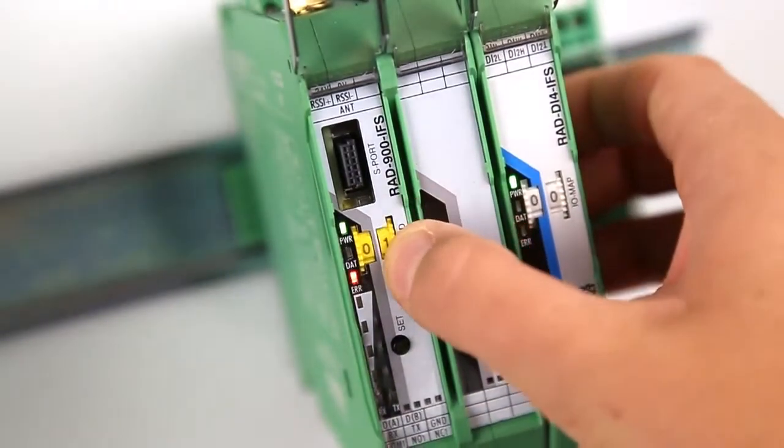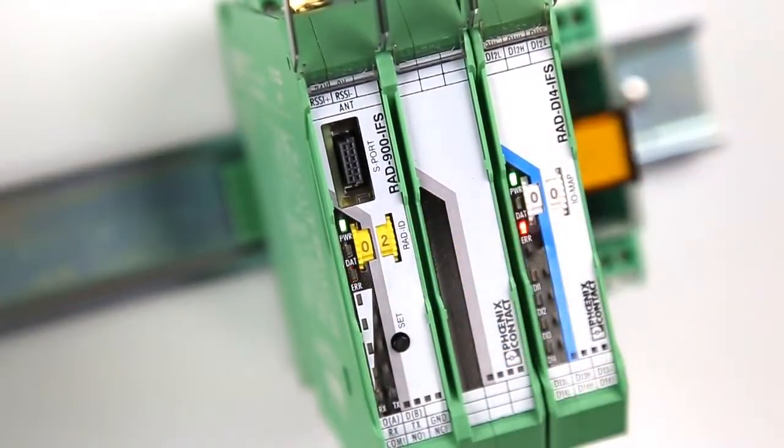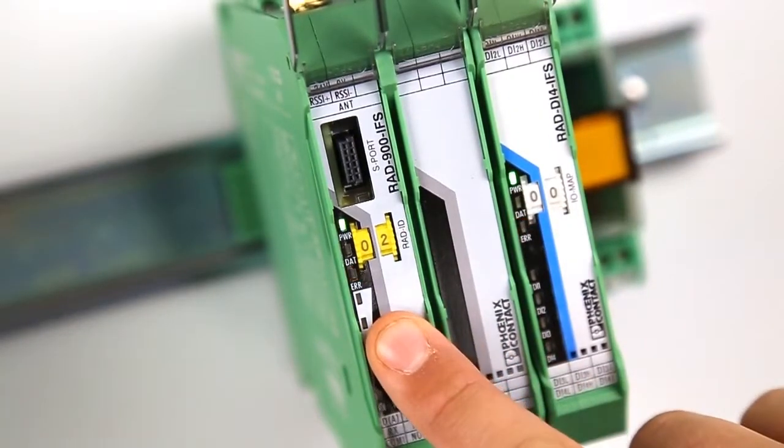We're going to configure the slave by setting the yellow thumb wheel to 02. To read in the thumb wheel setting, press the set button for one second.